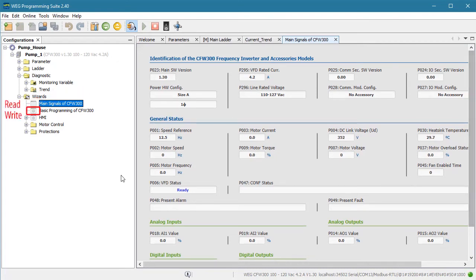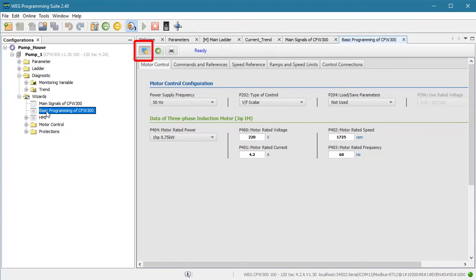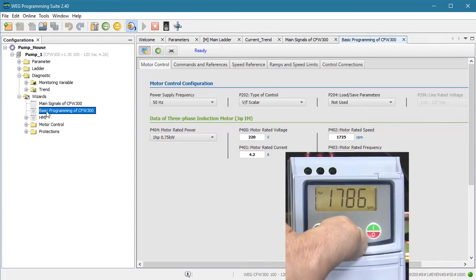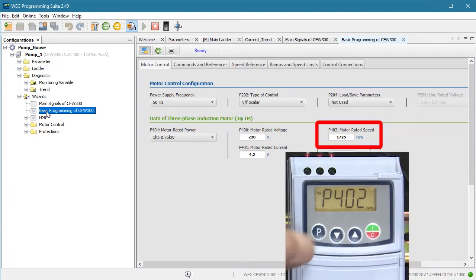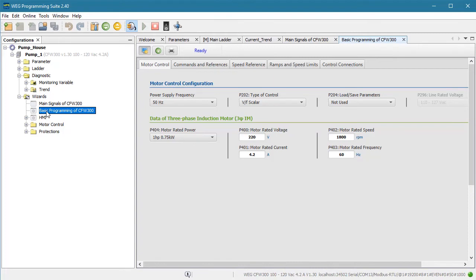Wizards with this icon have values you can change and have two buttons to help you manage that. The monitor button is already selected so WPS is polling the drive repeatedly right now and displaying the results on the screen. If I change parameter 402 on the drive, WPS shows the results on the screen. To write a value, you need to deselect the monitor button.